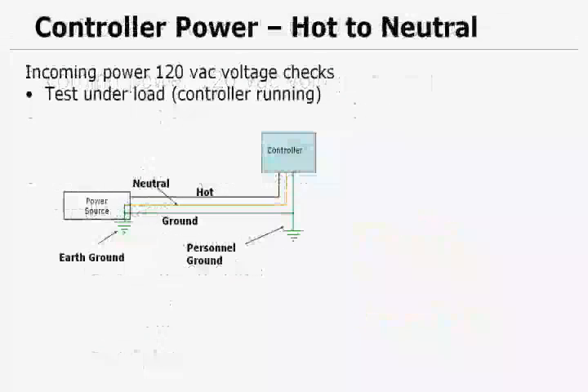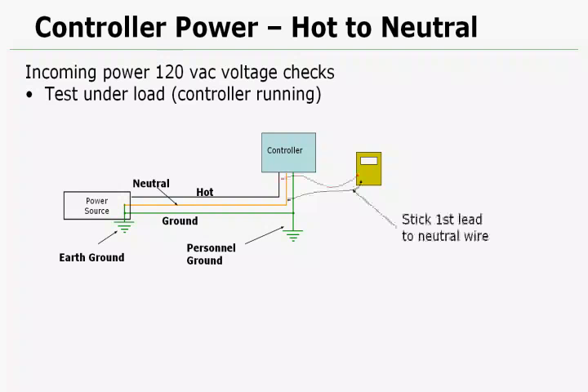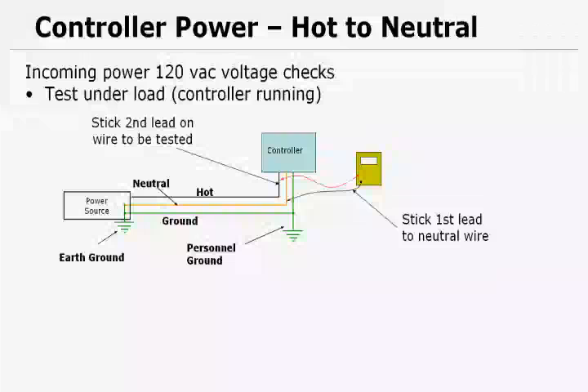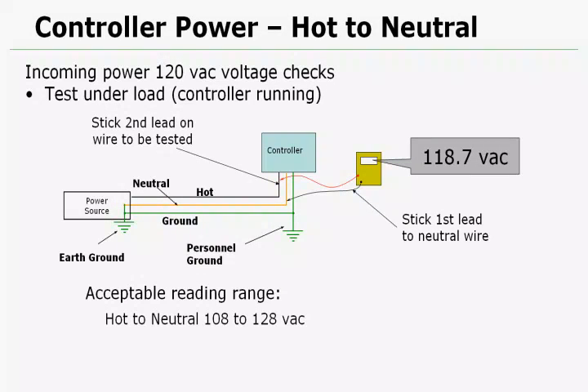Next test is hot to neutral. Test it under load, so have the controller running. First lead we're going to put to the neutral wire, second lead we'll put to the hot wire. Now we get a reading of, in this example, 118.7 volts. Acceptable readings here between 108 and 128.